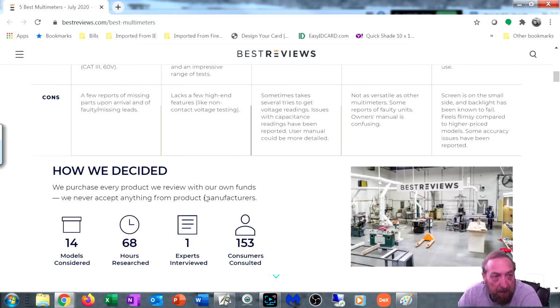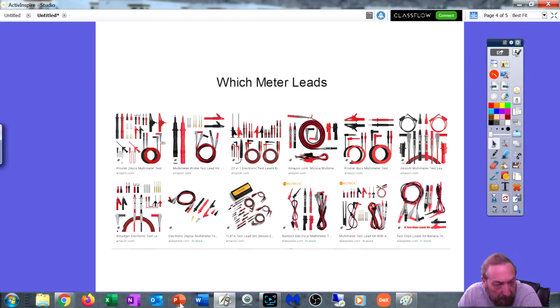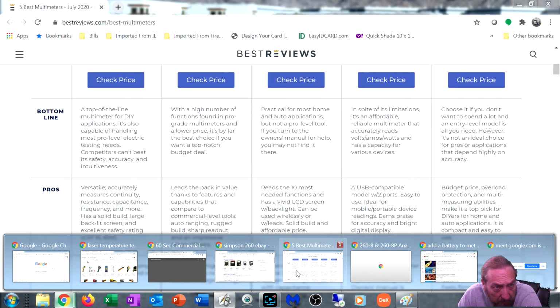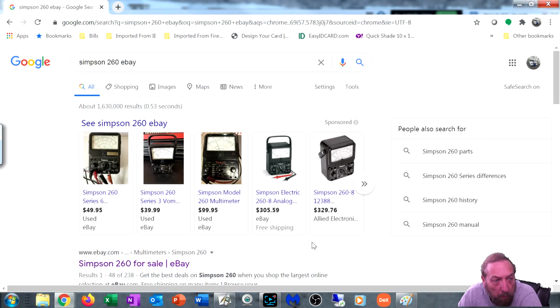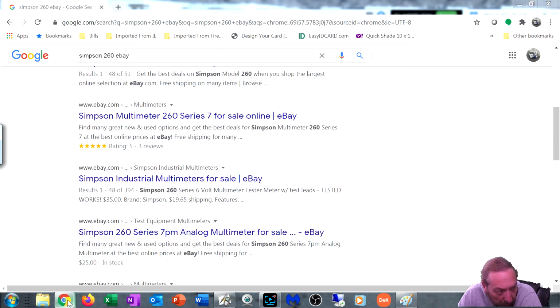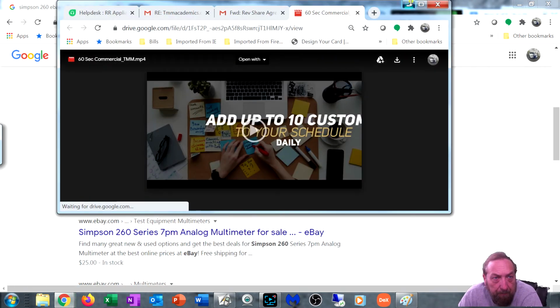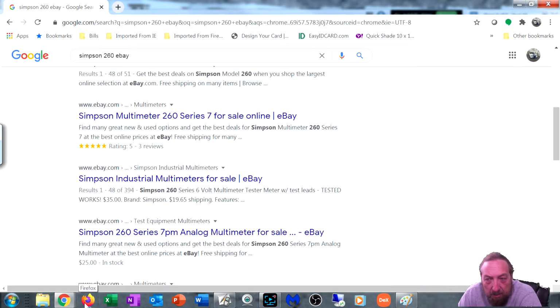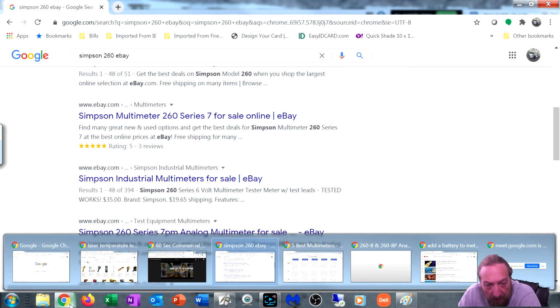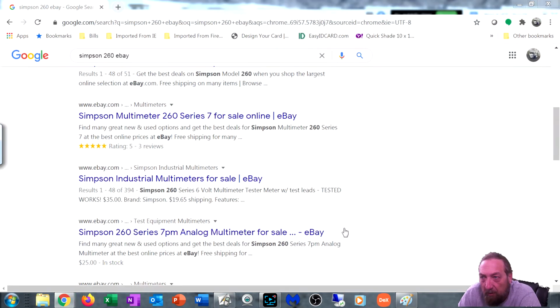voltage rating on them. And if we go back to that last meter we were just at, let me go back to that screen for one more second. I think it was this one. No, this one here. No, that's not the meter I was looking for. When we were looking at that other meter that did those tests, the maximum voltage rating of that meter is very important. Some of them are like 600, some are less. And you have to have the right voltage rating on your meter, because if your meter doesn't have it, it could jump voltage right through the face of the meter.